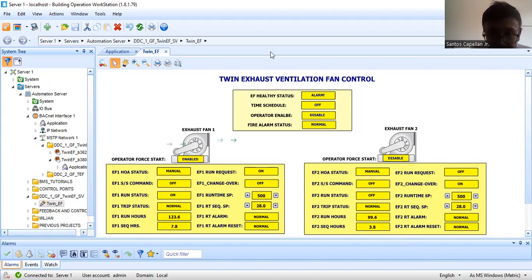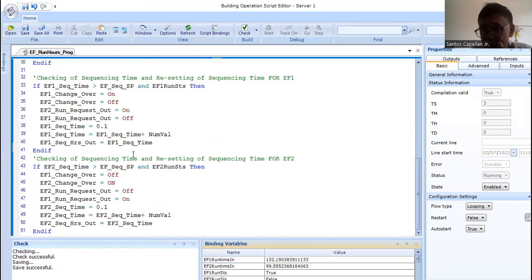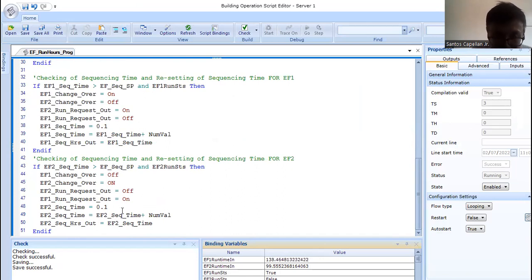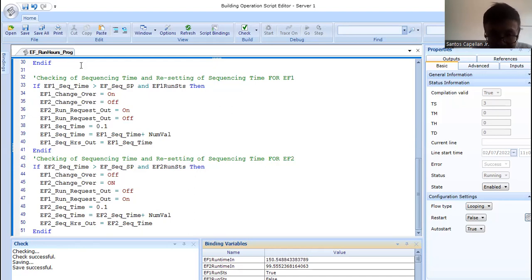The purpose of this program — let me show you again in the script — this portion is the one doing the changeover and changing of fan request, and resetting the sequencing time. I'm resetting it to 0.1, then again it will accumulate, then again it will be checked. Let's say EF1 is what is running now — it will not go to the EF2 condition because that condition is not true. From the end-if, it will check the other condition. If conditions are not met, it will go to the end-if, then go back to the top, scan each line instruction one by one, and it will be executed by the compiler.